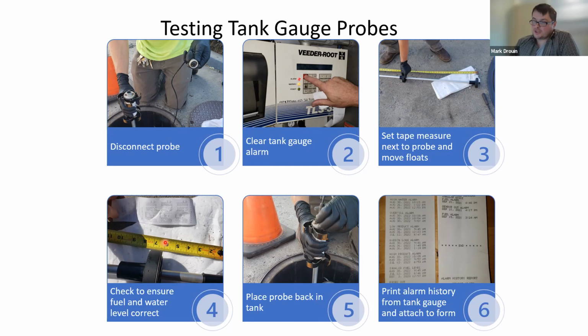You want to take one of those measurements. And here, when we were in the field, we tested this water float. What we did is we raised up this float until it triggered an alarm at the tank gauge. We printed out what it was supposed to be at. I forget, it was a few hundred gallons of water. We verified that with the tank chart, and we were good to go. So again, this is just a quick summation of what we did out in the field. When you're done with your testing and you're satisfied with it, you put the probe back in place, and then you print off your alarm history report.